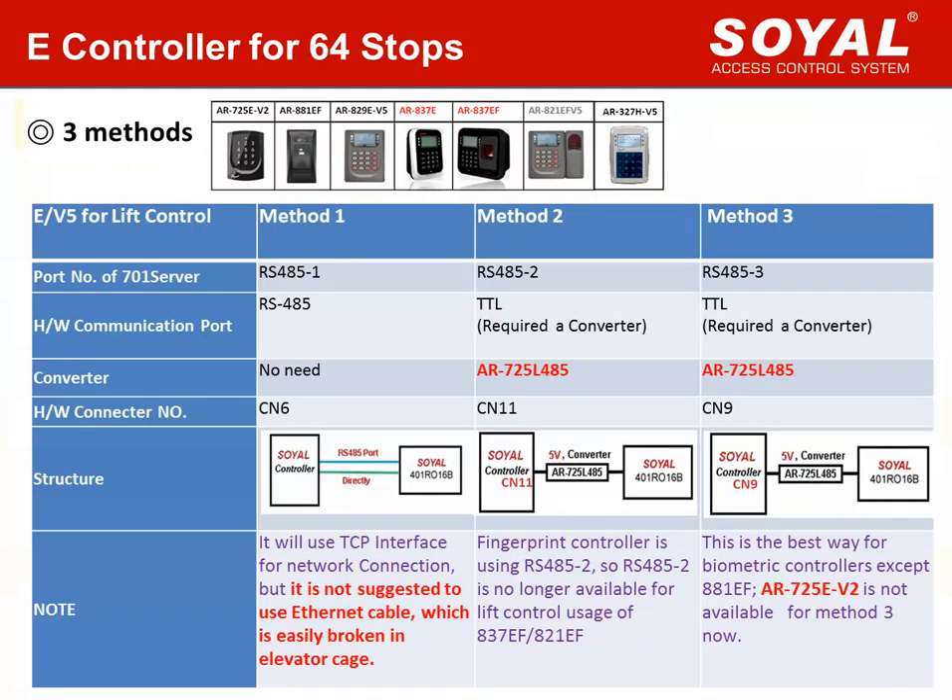Now let us introduce how to use the E-controller for lift control. We have learned that E-controller supports 64 floors and 16,000 user card capacity. Compared to edge controller, one more advantage is that E-controller provides three methods for lift control. Most E-controllers have three ports that can be configured for lift control. Method 1 can directly communicate with the lift control board without any converter. Methods 2 and 3 need a TTL converter. Method 1 uses the TCP/IP interface for networking, but it is not suggested to use an Ethernet cable, which is easily broken in an elevator cage.